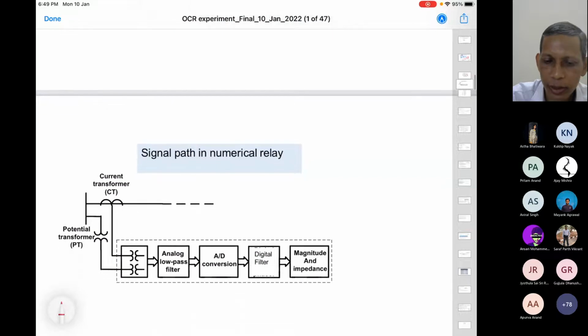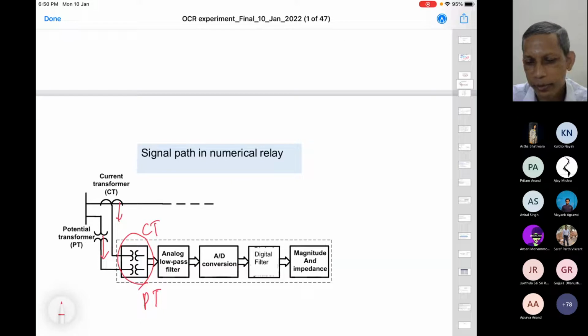If you see the signal flow path, the current or voltage signal is scaled down. Current is scaled down by the current transformer, 100:5, 1000:5, 800:5, that kind of transformation. And voltage also, for a 100 kV system, 132 kV system, 400 kV system, the corresponding voltage has to be scaled down to 10 volt, 5 volt, by the potential transformer. Then we have an analog low pass filter so that spikes etc. can be avoided, for the security of the electronic device. Then you have the analog to digital conversion, and then your digital filter.